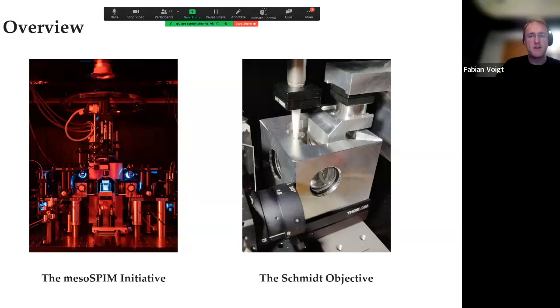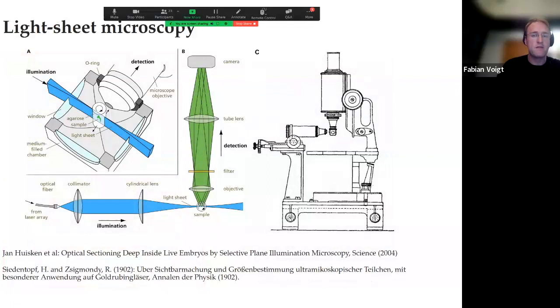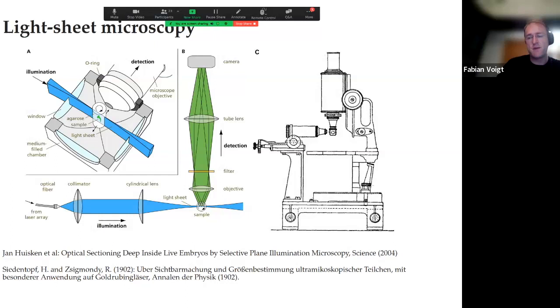The other system involves an uncommon approach to build microscope objectives, oriented towards providing very high data quality out of cleared tissue. Regarding light sheet microscopy, in my view there are two big worlds, and the dividing line is sample size. For live imaging like developing zebrafish or drosophila embryos, you deal with samples on a millimeter scale. For cleared samples many centimeters in size, your microscope has to grow with the sample — the objective working distances used in classical light sheet microscopy for developmental imaging become limiting for clear tissue imaging. You can't optimize perfectly for both at the same time.